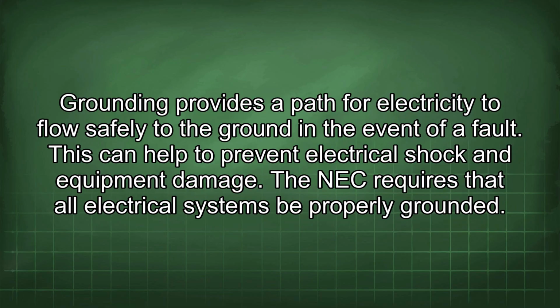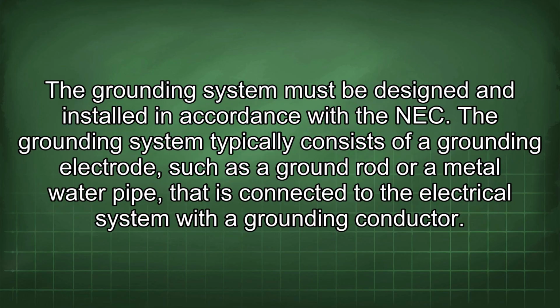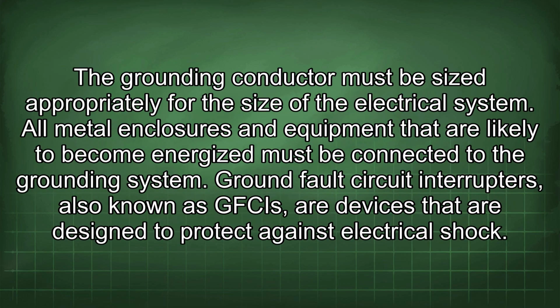Grounding provides a path for electricity to flow safely to the ground in the event of a fault. This can help to prevent electrical shock and equipment damage. The NEC requires that all electrical systems be properly grounded. The grounding system must be designed and installed in accordance with the NEC. The grounding system typically consists of a grounding electrode, such as a ground rod or a metal water pipe, that is connected to the electrical system with a grounding conductor. The grounding conductor must be sized appropriately for the size of the electrical system. All metal enclosures and equipment that are likely to become energized must be connected to the grounding system.